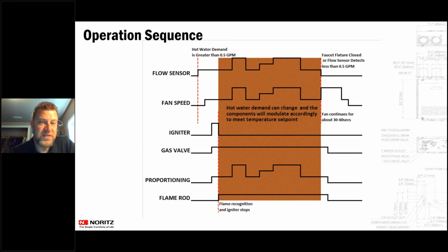We do have units with a super low BTU mode where it will modulate down to about 5,000 BTUs. So our minimum BTU is still 18,000, but with that super low BTU mode, it'll go down to about 5,000 BTUs.